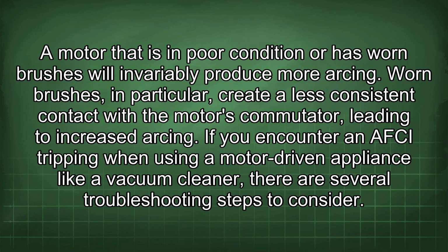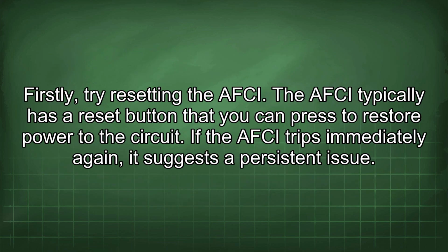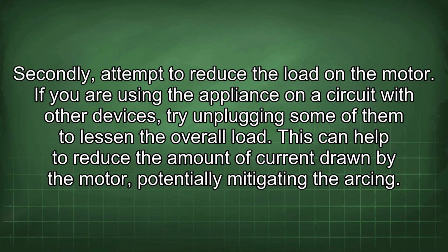If you encounter an AFCI tripping when using a motor-driven appliance like a vacuum cleaner, there are several troubleshooting steps to consider. Firstly, try resetting the AFCI. The AFCI typically has a reset button that you can press to restore power to the circuit. If the AFCI trips immediately again, it suggests a persistent issue. Secondly, attempt to reduce the load on the motor. If you are using the appliance on a circuit with other devices, try unplugging some of them to lessen the overall load. This can help to reduce the amount of current drawn by the motor, potentially mitigating the arcing.